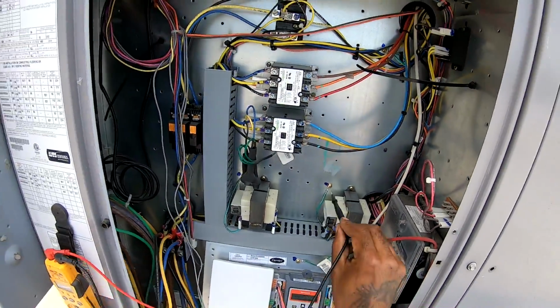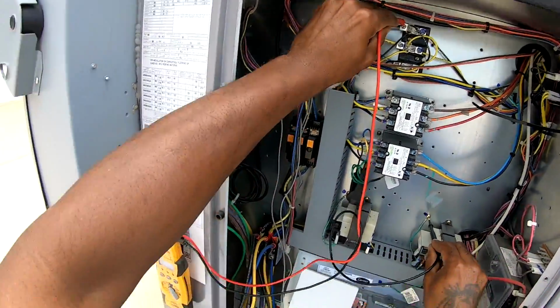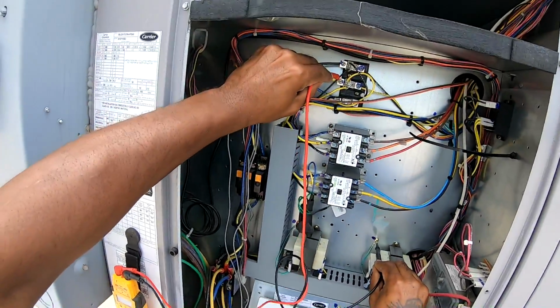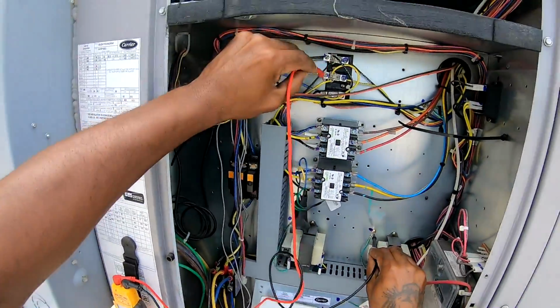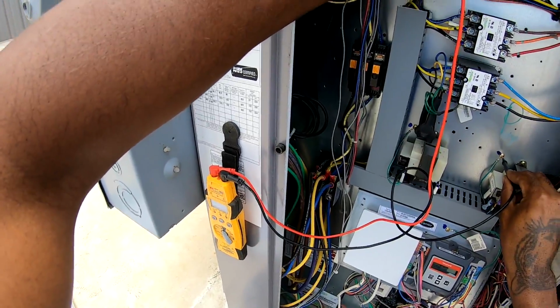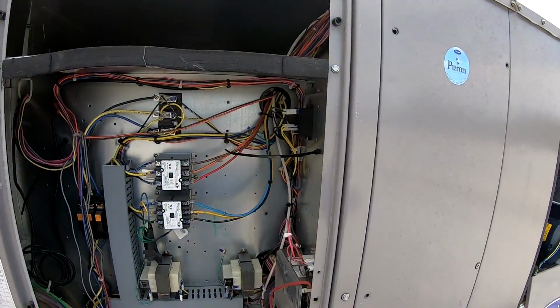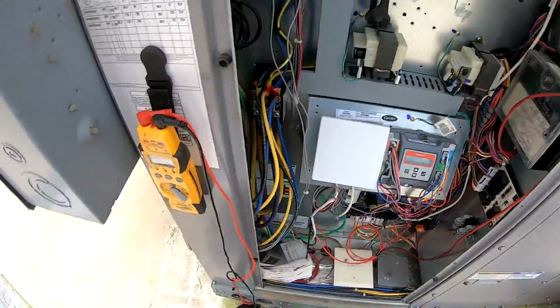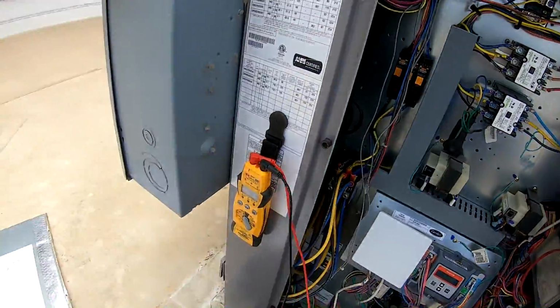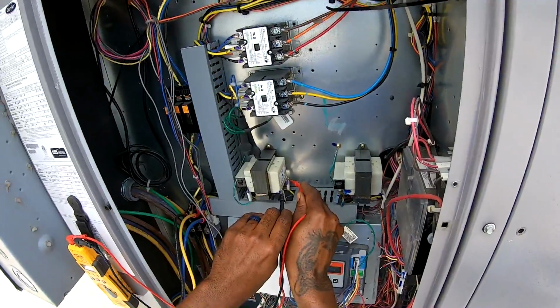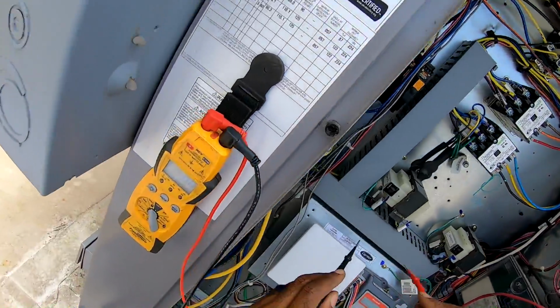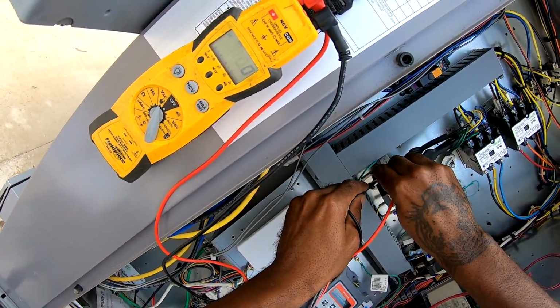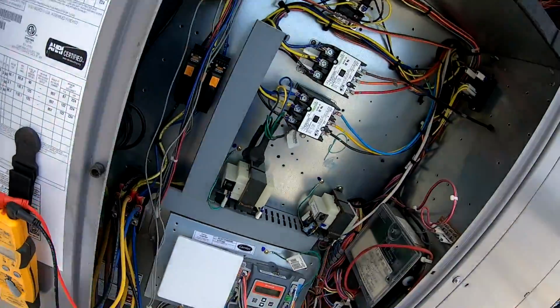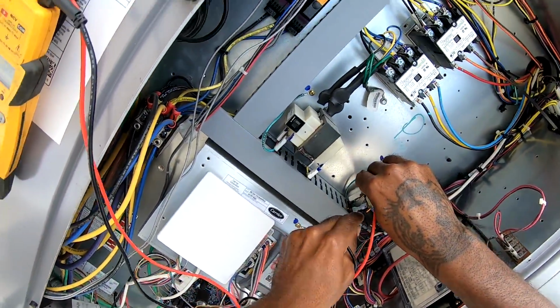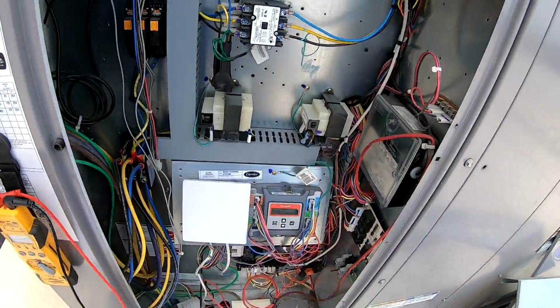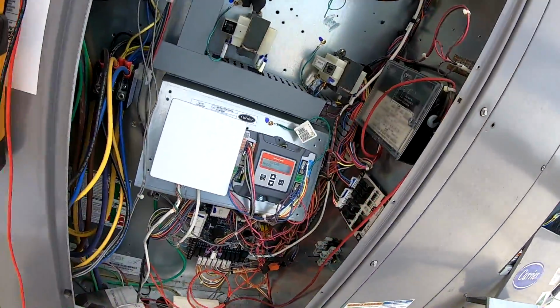So I know my fuses should be good. Going from leg to leg, I got 277, 277, and 279, so I shouldn't have any voltage issues. Let's see. Got 480 on that side, 277 on that side, 277 on that side. So the transformers are good.